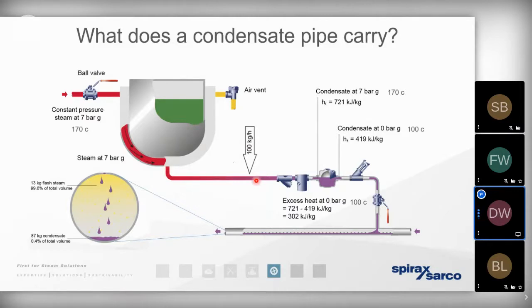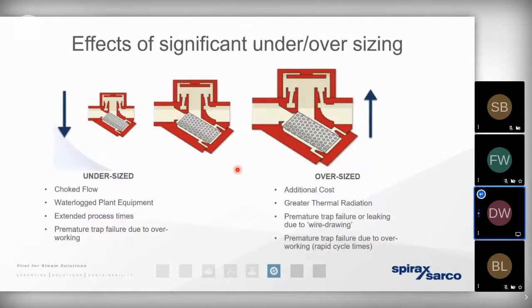If this pipework were undersized, we run the risk that that condensate could back up and start to flood the process, at which point we've got a barrier to heat exchange. So sizing the pipework is important, but it's equally important to ensure that we've sized the trap itself correctly. Now, an undersized trap is going to be self-explanatory. We could leave the condensate backing up to waterlog the network or to waterlog the heat exchanger, which is going to cause us problems. But we can have just as many problems by oversizing the trap. That's because if we oversize the trap, it's far more likely that the disc or the valve seat is going to be operating far, far closer together for prolonged periods of time. So that's when we're going to get a trap failure through excessive erosion or abrasion.